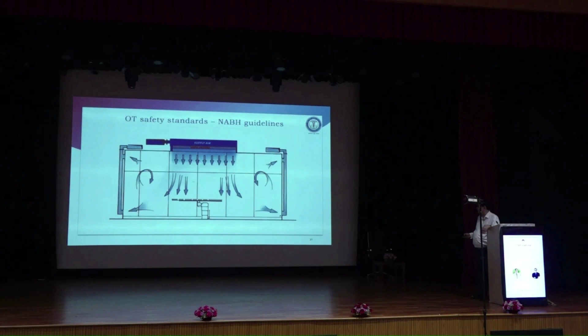Very important - you engineers may know about HEPA filters, the high efficiency particulate air filters, which are in the AC ceiling and filter out 99.97%. So this is the supply of air, coming from the top. This is the OT table, patient lying here. Air comes and finally moves away, maintaining sterility at all times.